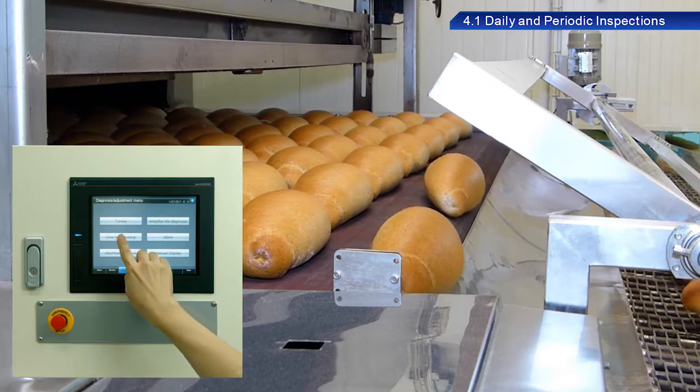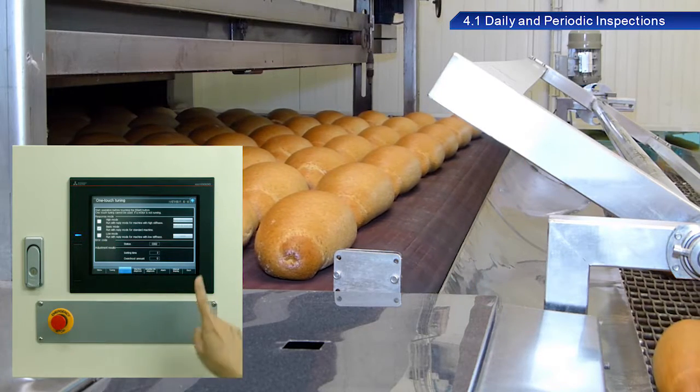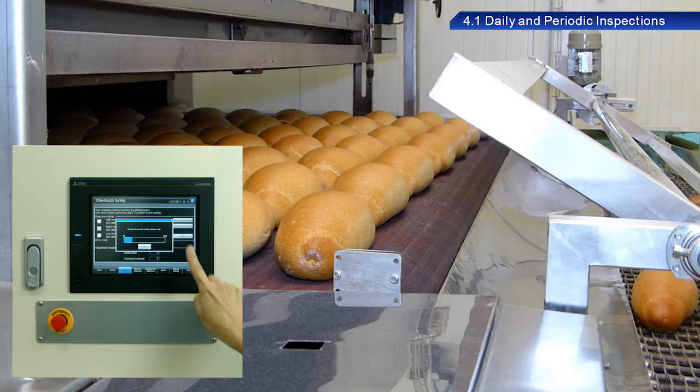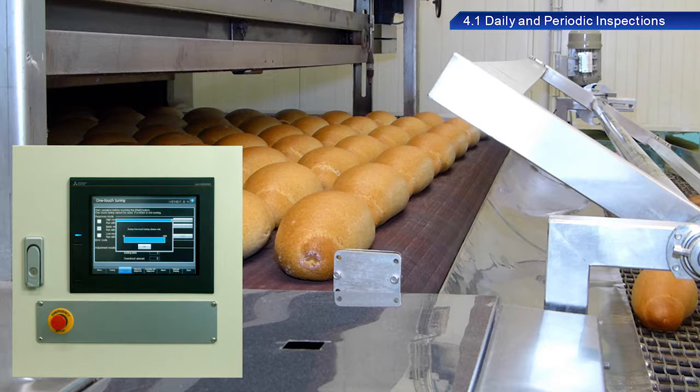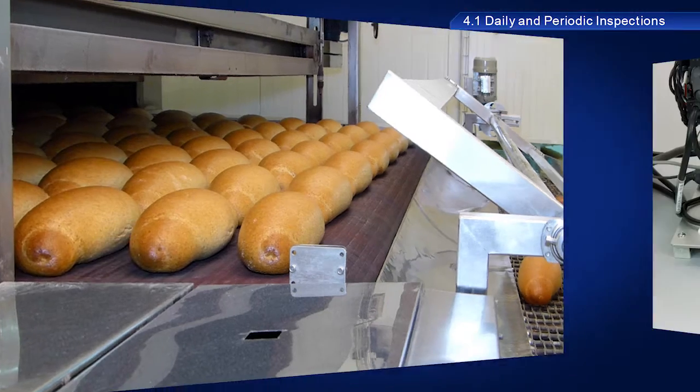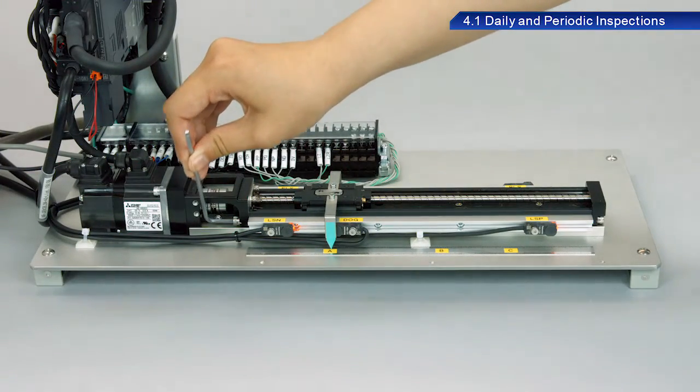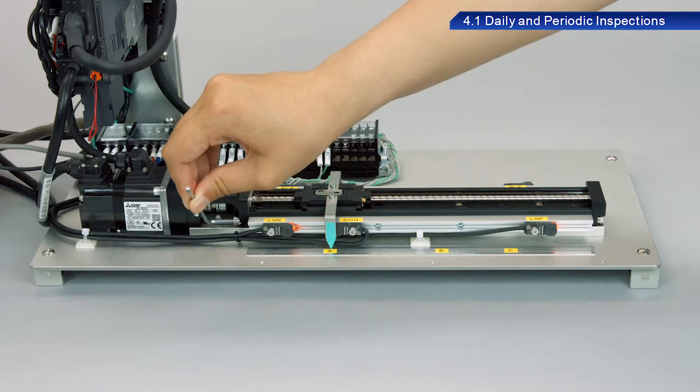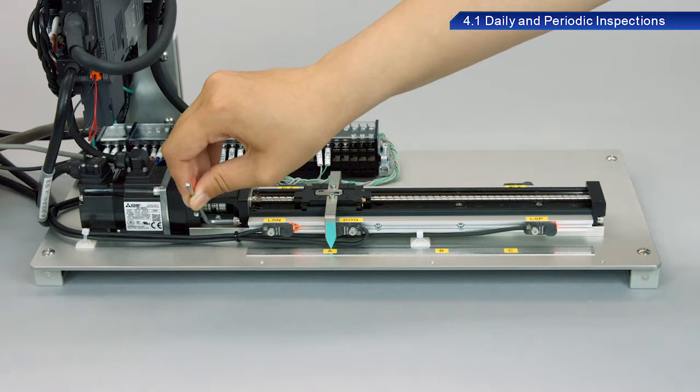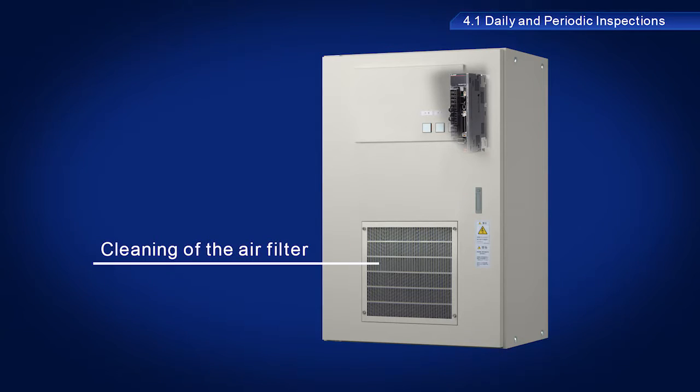Periodic inspections are used to stop equipment and perform checks not possible while operating. Screws, bolts, and other fittings may loosen due to vibration or temperature changes. Fittings should be checked during periodic inspections to ensure they are tightened properly. The air filter should also be cleaned as part of these inspections.